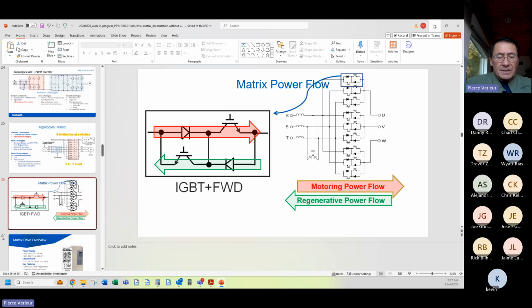When we put 3 of these units in, 3 350 horsepower units into the Whittier Narrows water reclamation plant, which was done well over a decade ago, we replaced 3 18-pulse systems, and the power factor went to 0.98 on that 1,000 horsepower worth of drives, which was a significant portion of the power draw on the plant. Southern California Edison, a couple of weeks later, called the plant manager and said, "We're coming in to do an inspection." They didn't ask, they just said they're coming in. They suspected that this plant, because of the drastic change in the power factor, was cheating and pulling power from somewhere and not paying for it. That's how drastic the effect is when you put matrix drive in versus the old technologies. You immediately elevate the power factor to 0.98.